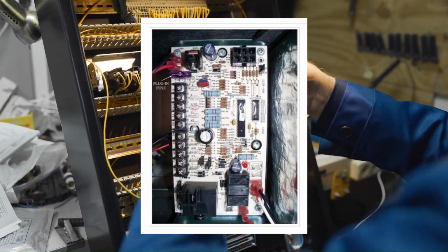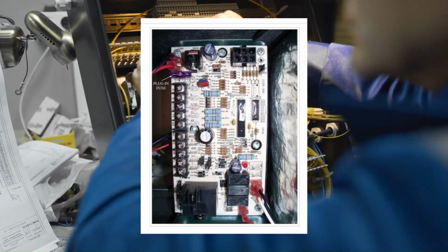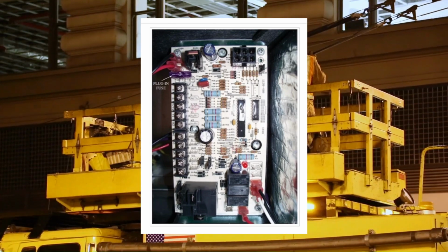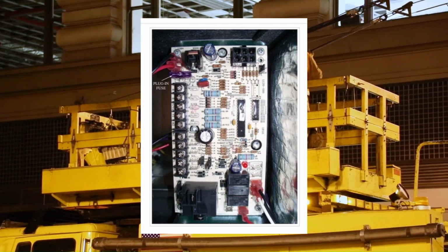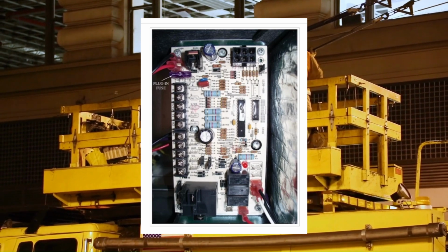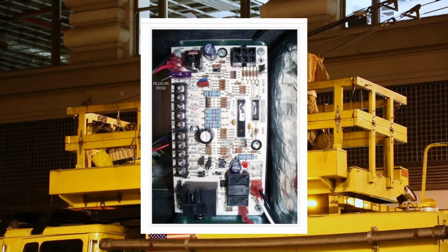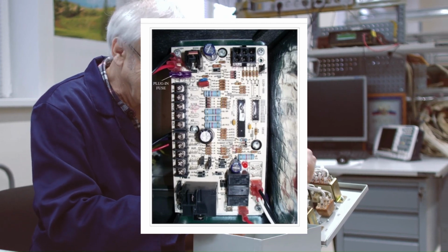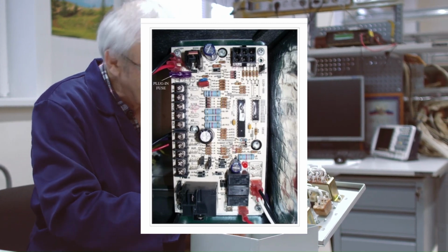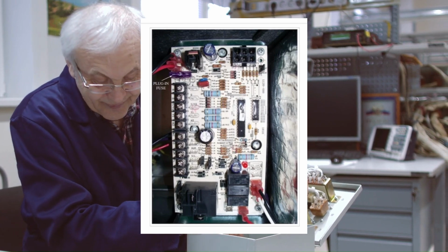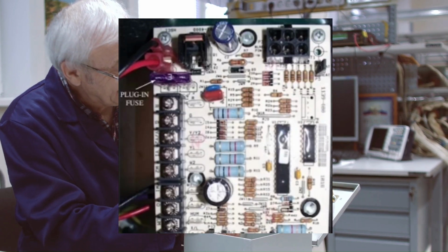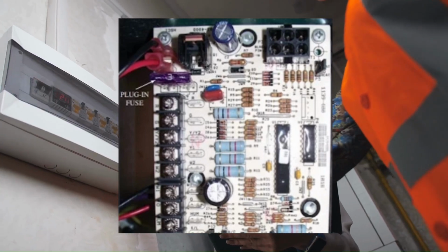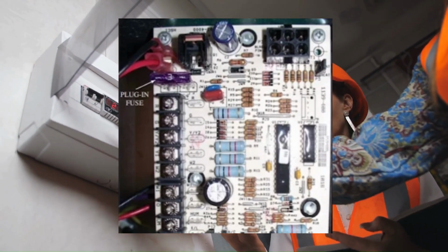The breaker typically matches the maximum amperage specified on the nameplate of the electrical heating unit in terms of rating. To apply the proper size breaker, the installing contractor may need to examine the installation's amperage values. It may be necessary to specify a breaker with an amperage that is 115% of the unit's maximum amperage. It is not advisable to utilize a breaker that is too large.